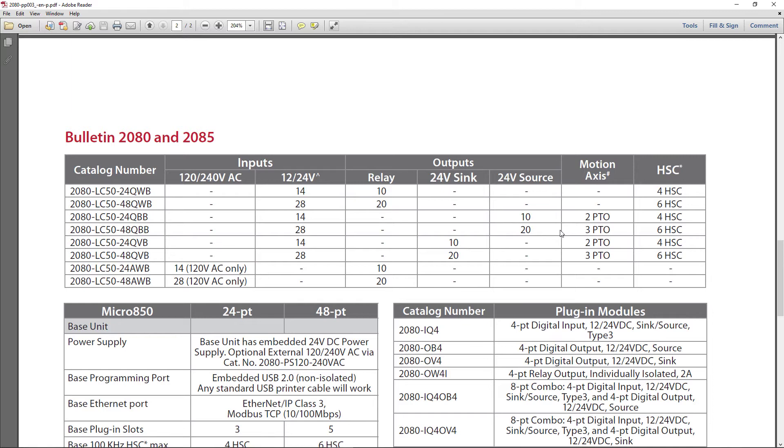The 48 QBB that I use: 28 inputs and 20 outputs. It's all straight up DC. The important thing to notice is that the 48 QBB has three pulse train outputs and the 24 only has two. Notice it also has more high-speed counters than the 24.